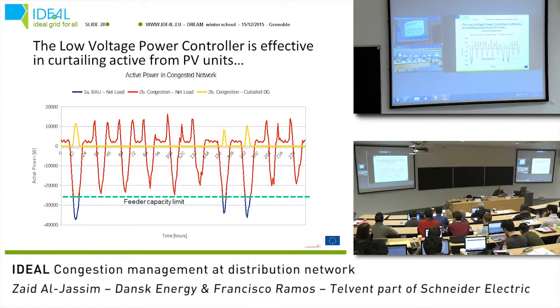If I explain this figure, the green dotted line shows the maximum feeder capacity limit, and the blue line shows the production of the PV units. The power controller forecasts, or can see, that there is a congestion in the network, that the capacity limit of the feeder has been exceeded, so it curtails some of the active power generated by the PV units, as shown in the yellow line. And the result is the red line, which shows the active power production from the PV units after the curtailment by the power controller.